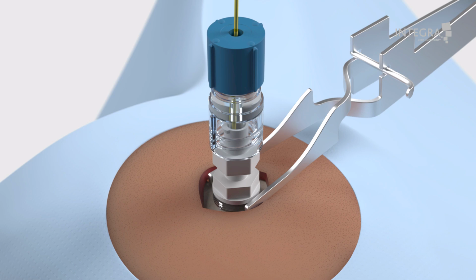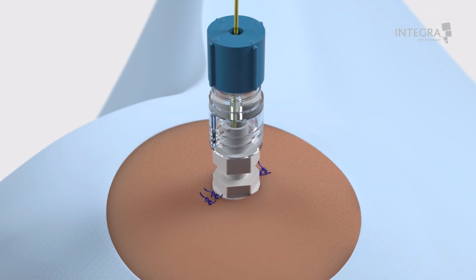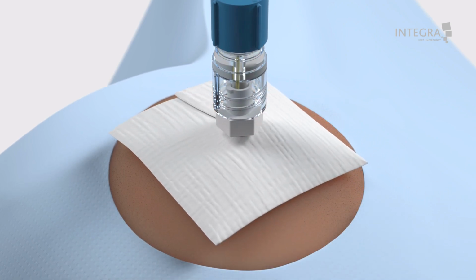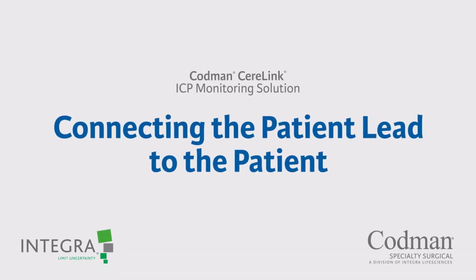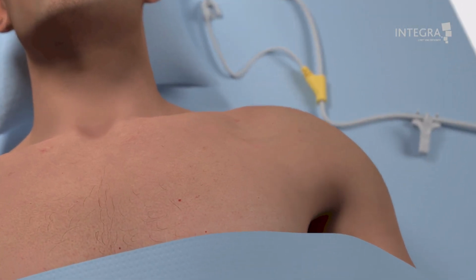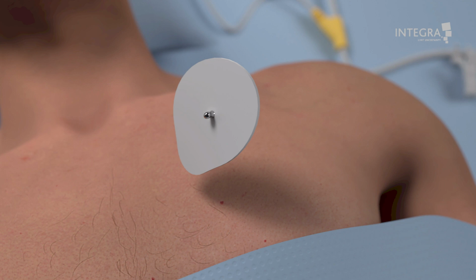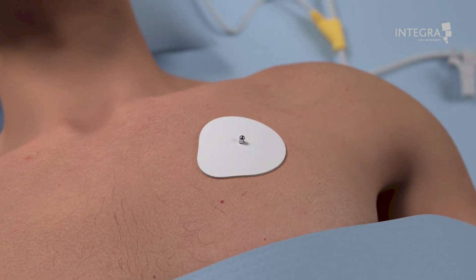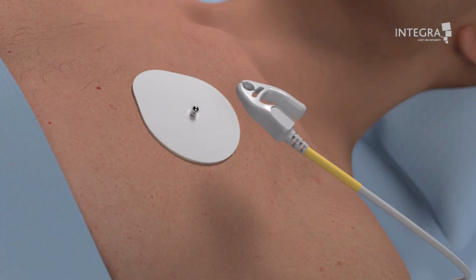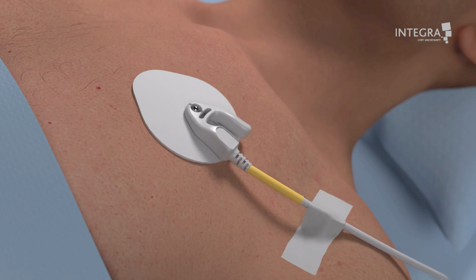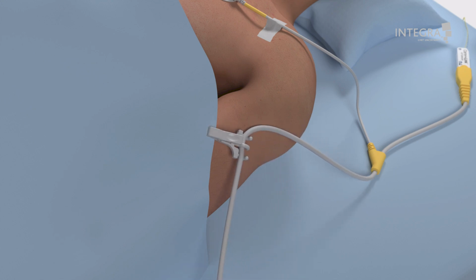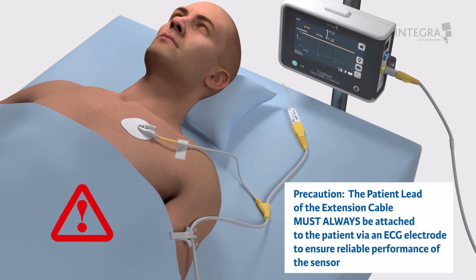Remove the retractor and close the skin incision in one layer using interrupted sutures. Apply appropriate dressing to the wound site. Attach any off-the-shelf ECG electrode to the patient per ECG electrode's instructions for use. ECG electrodes should be applied only to intact, clean skin. For example, not over open wounds, lesions, infected or inflamed areas. Attach the patient lead of the extension cable connector to the ECG electrode. Secure the patient lead of the extension cable to prevent tension on the ECG electrode. Precaution: the patient lead of the extension cable must always be attached to the patient via an ECG electrode to ensure reliable performance of the sensor.